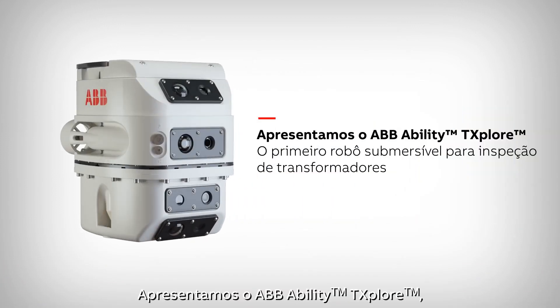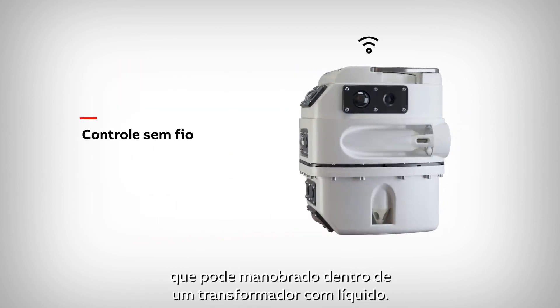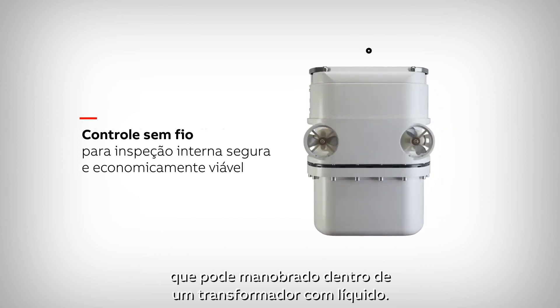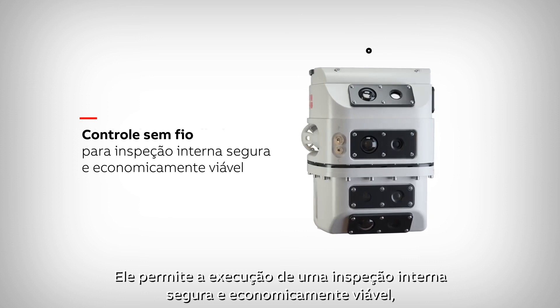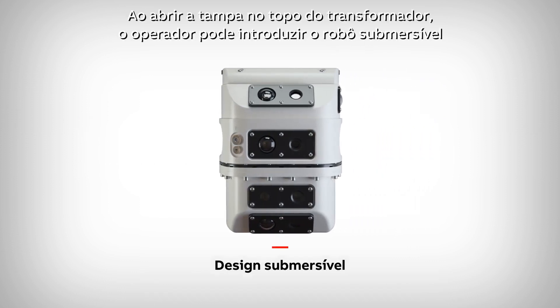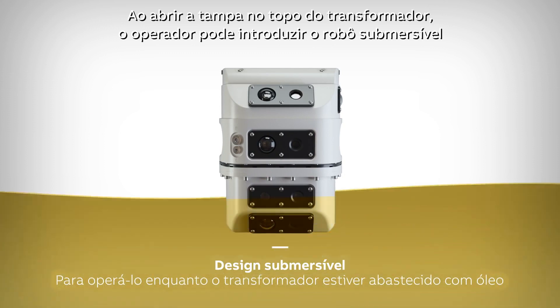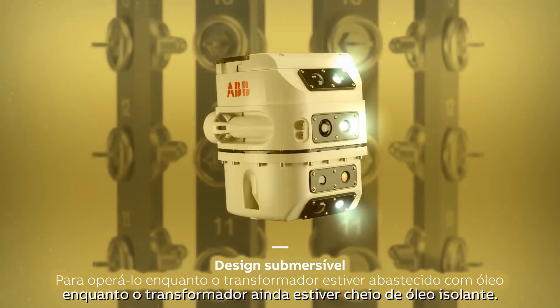Introducing ABB Ability TXplore, the first submersible transformer inspection robot. Wirelessly controlled, it can be maneuvered through a liquid-filled transformer to perform a safe and cost-effective internal inspection that can be viewed remotely. Opening the cover on top of the transformer allows an operator to introduce the submersible robot while it is still filled with oil.